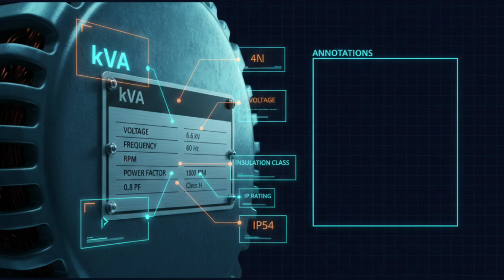Nameplate data and ratings. Every alternator is fitted with a manufacturer's rating plate containing crucial technical information that engineers must interpret correctly. This includes apparent power in kilovolt ampere, rated line voltage, operating frequency, synchronous speed in revolutions, rated power factor, insulation class which indicates thermal limits, and IP protection class describing enclosure sealing.